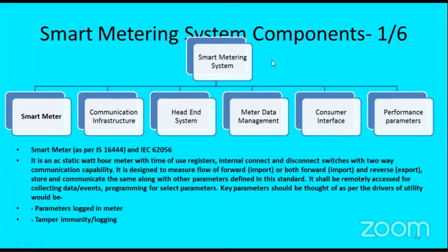What is actually a smart meter? The smart meter will conform to Indian standard specification 16444 or IEC 62056. It gives you all information, and this can probably be given as course material too. It is an AC static watt-hour meter with time-of-use register, internal connect and disconnect mechanism, with bidirectional communication facility. It is designed to measure forward, import, backward, export of power, reverse power, and to store and communicate the same along with other parameters defined in the standard.